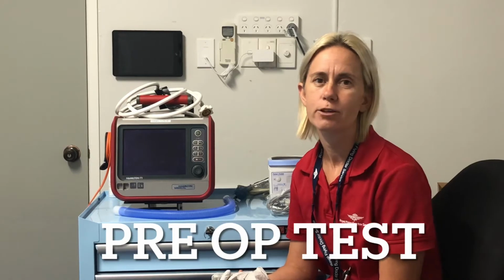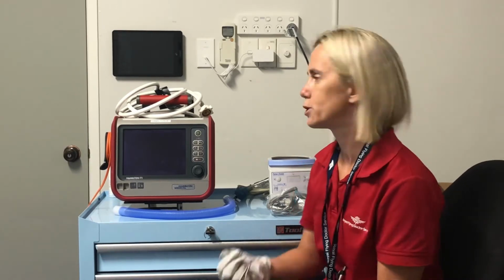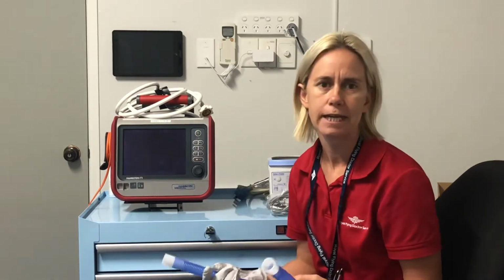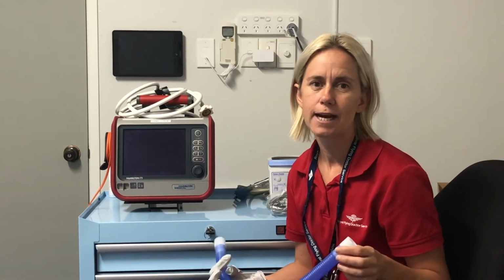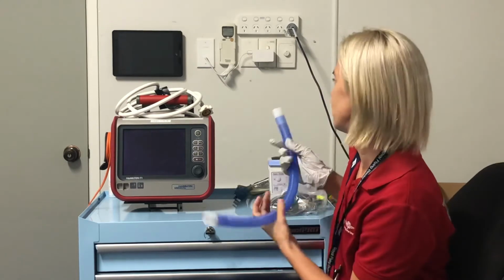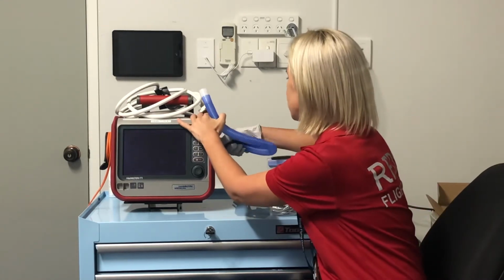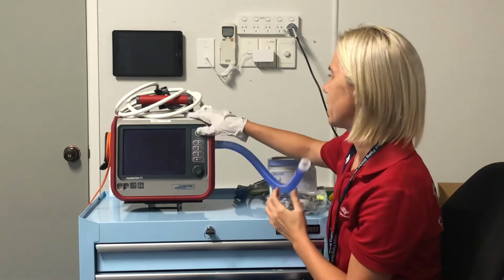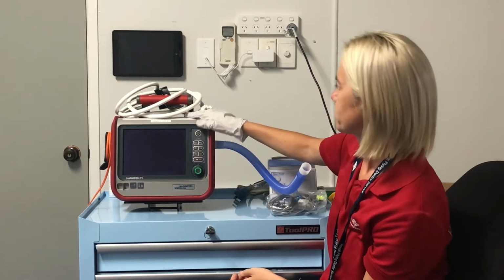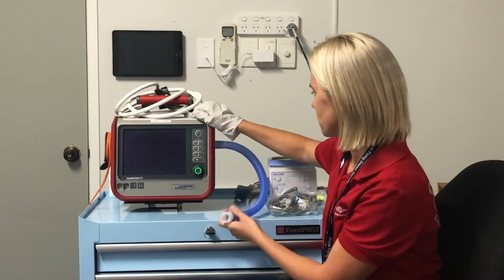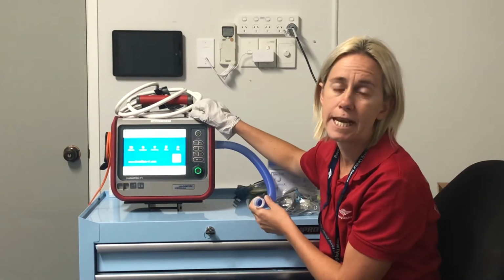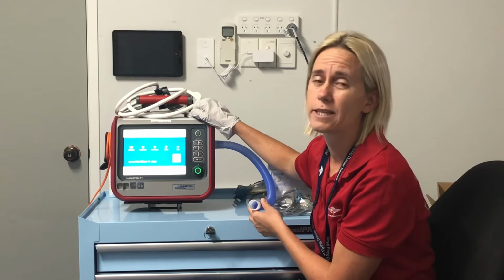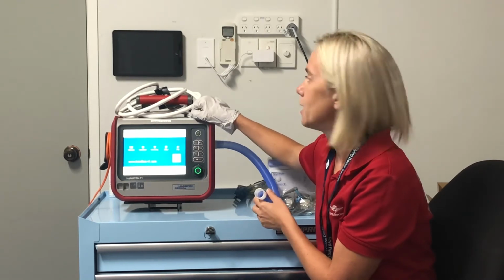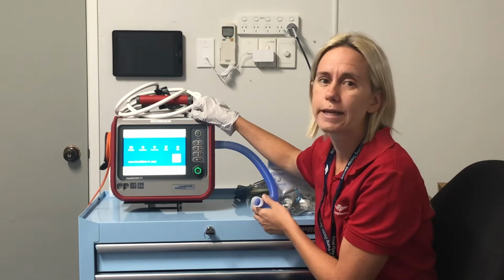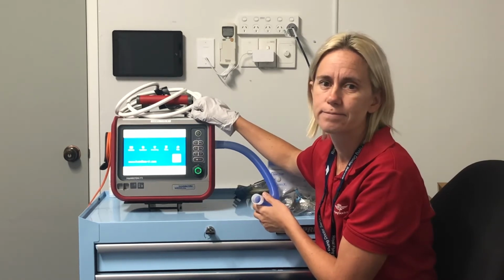Okay, we're back. So next we're just going to run through doing the high flow pre-op test. So what I will do initially is get the RT024 circuit and put that on the Hamilton ventilator. So you just connect to that, to the inspiratory port, and then we're going to turn the ventilator on with the on button. So this is a pre-op test. This should be completed before commencing high flow, just to ensure that your Hamilton monitor is working appropriately and it has, I guess, that flow rate.